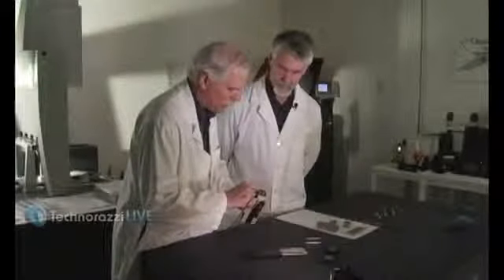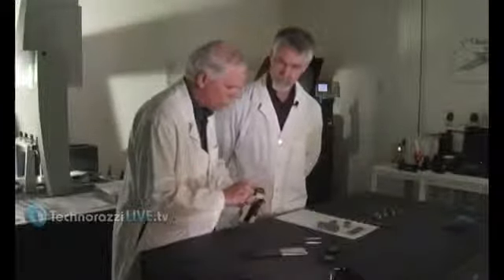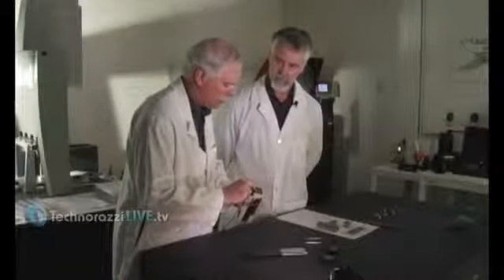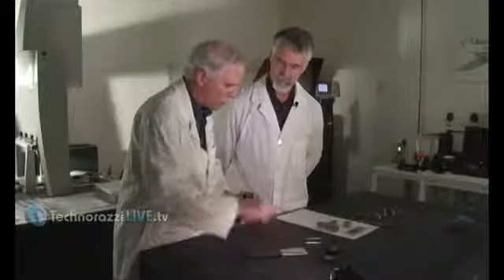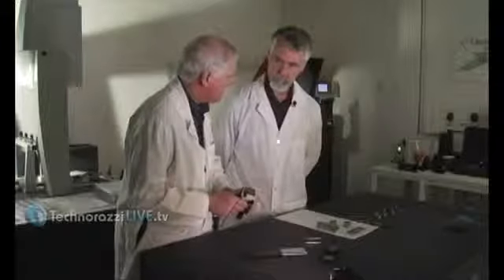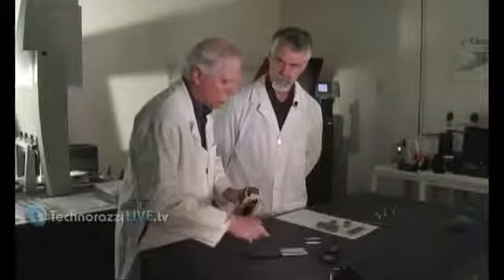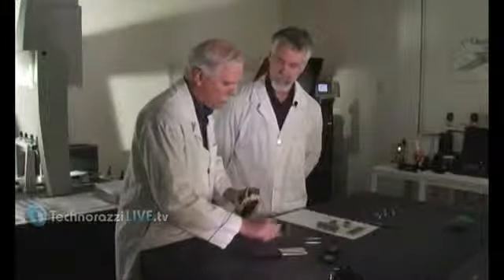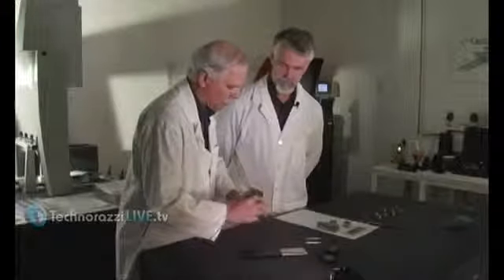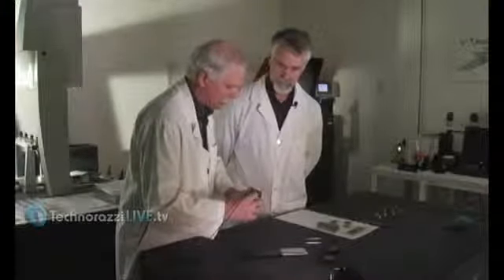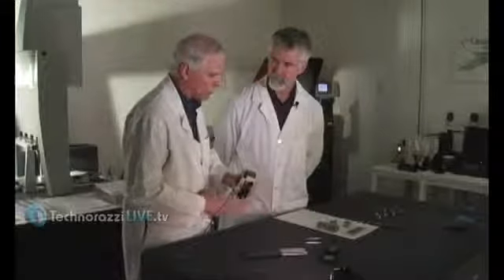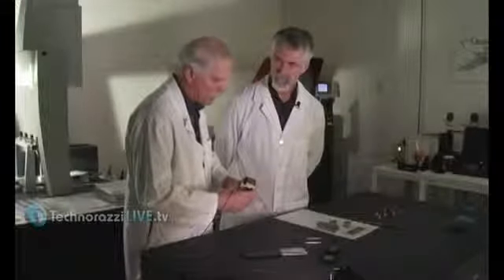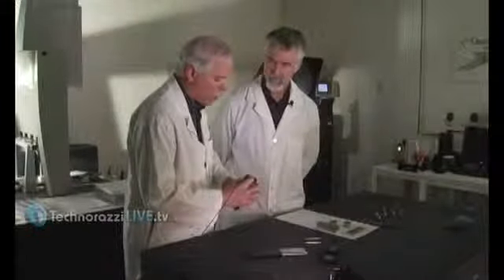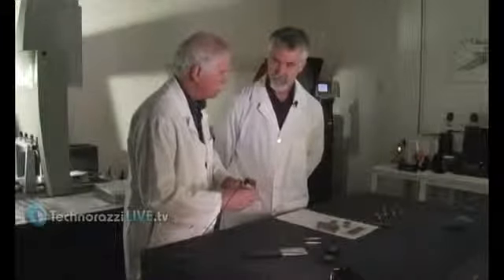One of the most important is the cutoff frequency. The cutoff frequency, which one you choose, you have 3 choices. It's determined by the roughness that you're going to be measuring. Okay. Use a higher cutoff frequency for the rougher, and you would use a lower cutoff frequency for the finer materials. What it's doing is filtering out random noises, waviness, things of that nature. And if you're set up with the wrong cutoff frequency, your numbers will be meaningless.